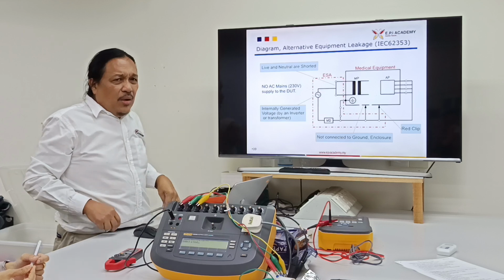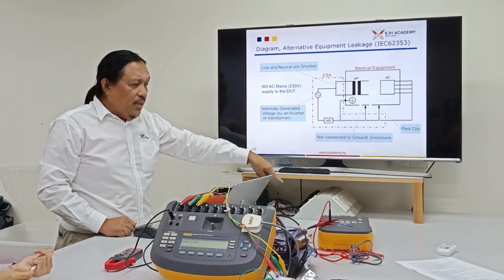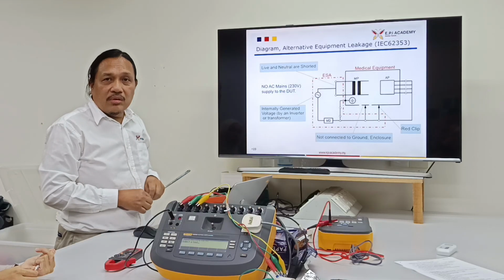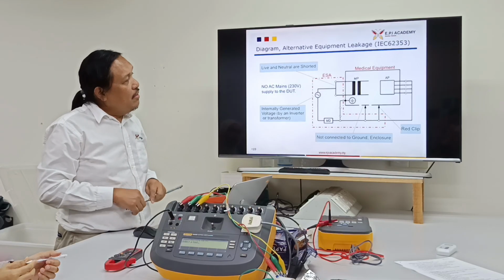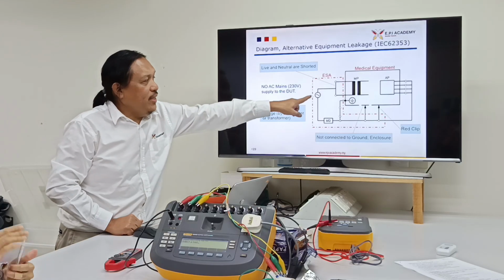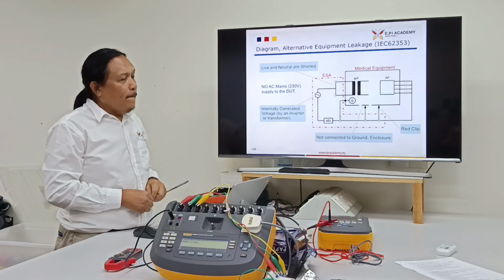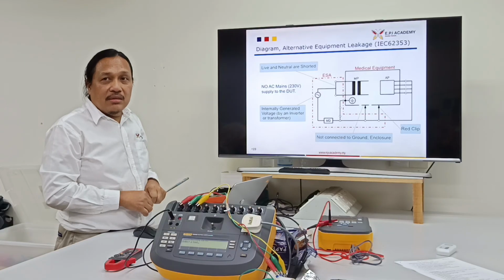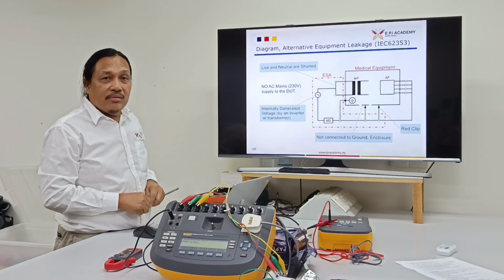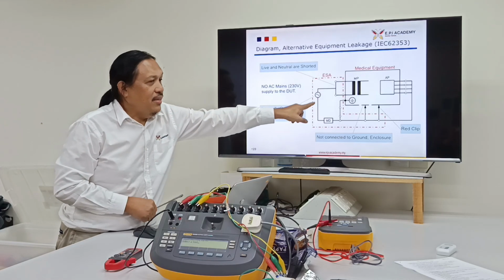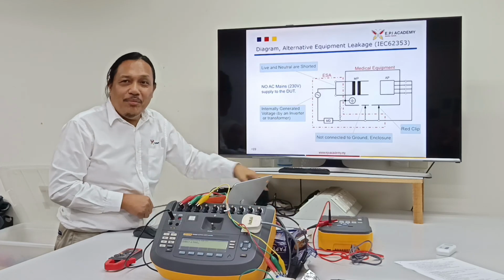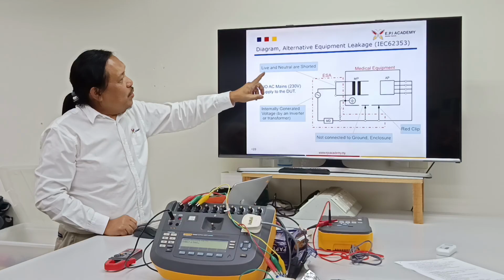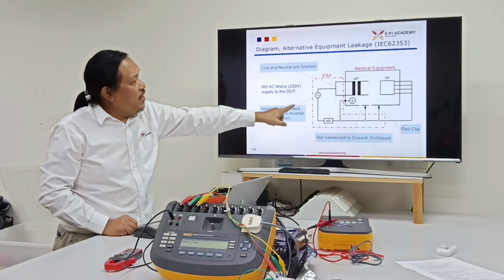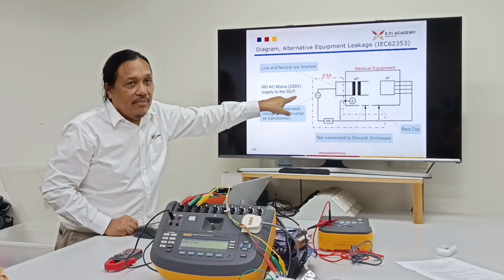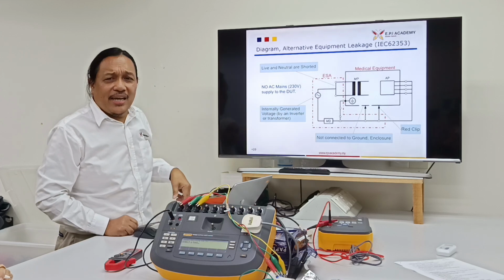What did we remove here? We just removed the 230 volt source. We removed it, and we substituted it with this, another voltage, internally generated. That's why this leakage is not accurate, because we substituted the voltage. It's not the voltage from here anymore. But anyway, in the requirement of IEC 62353, this voltage must be the same, but not exactly the same as the actual one.